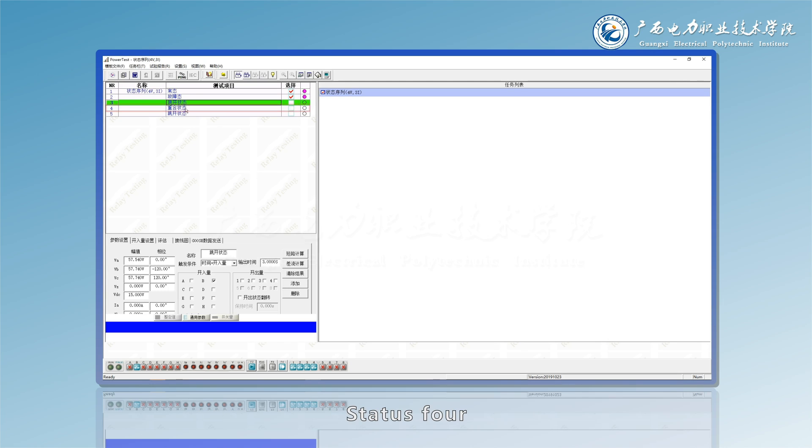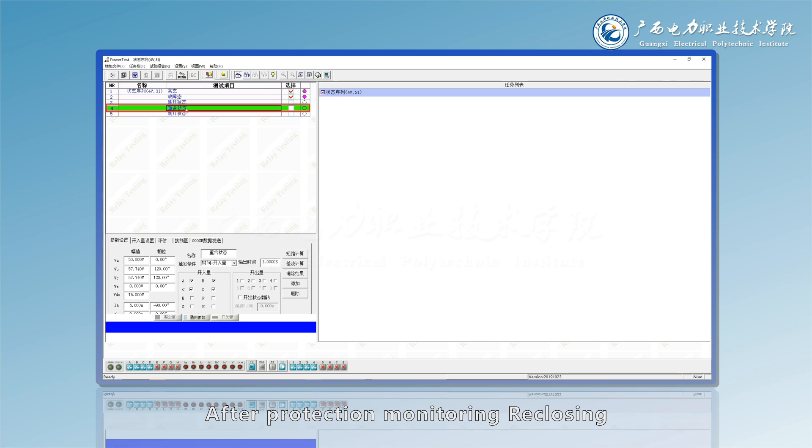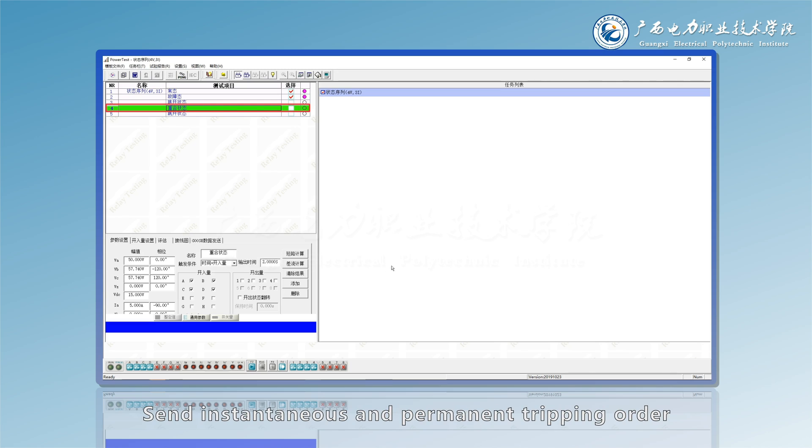Status 4: after protection monitoring, reclosing, the short circuit fault is still present, send instantaneous and permanent tripping order.